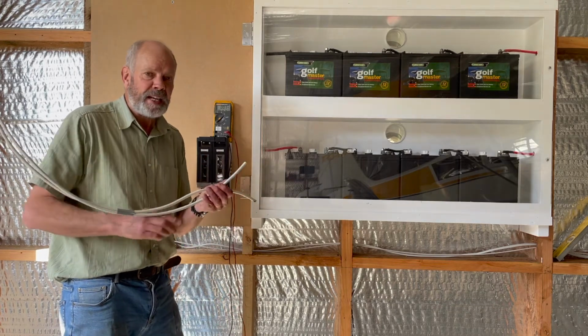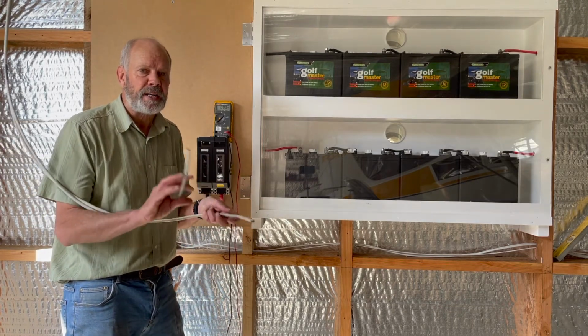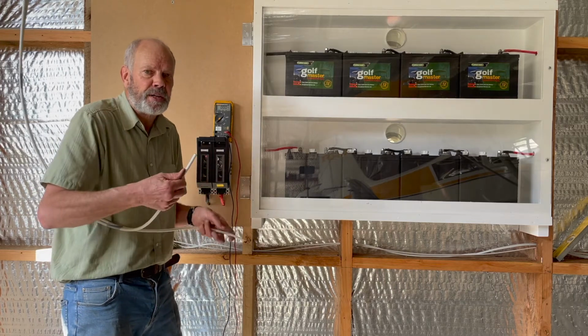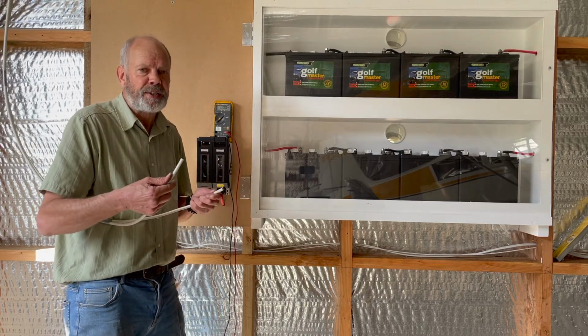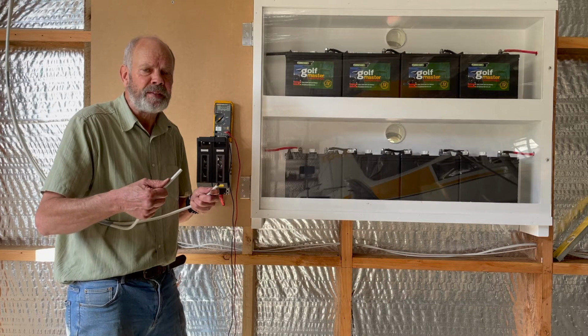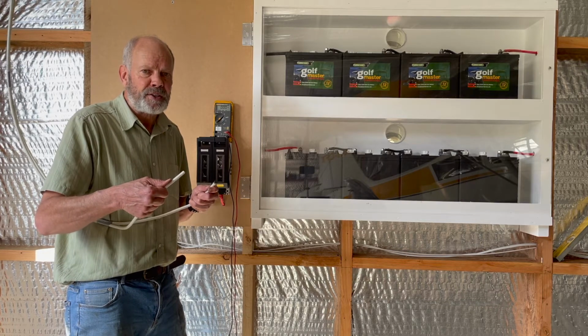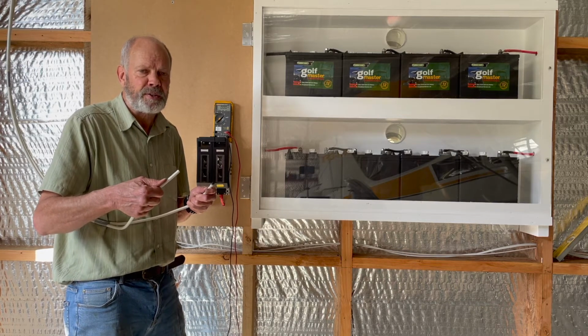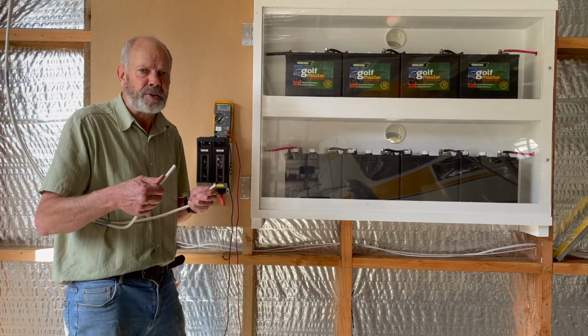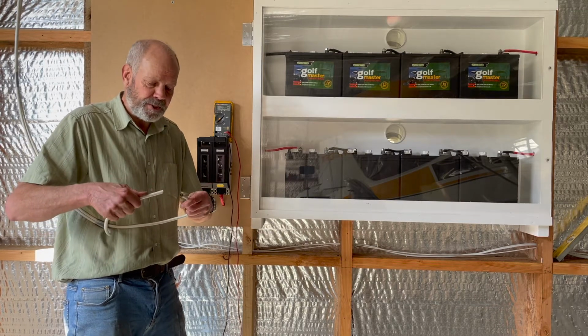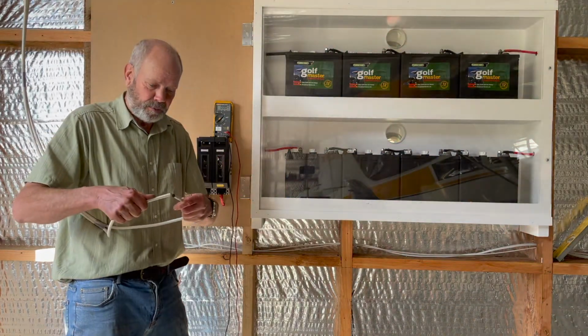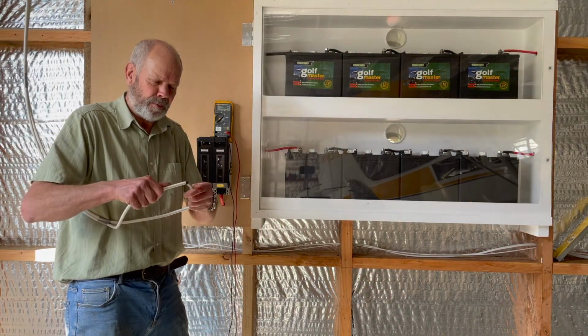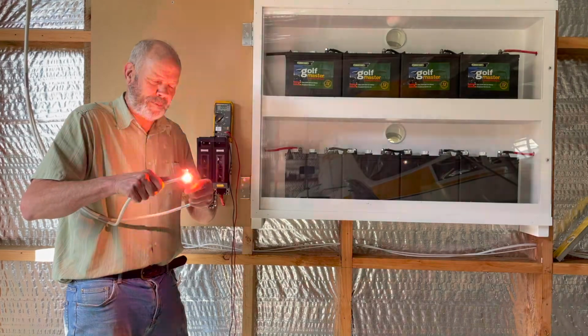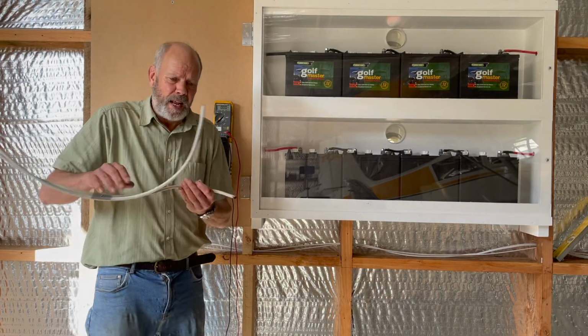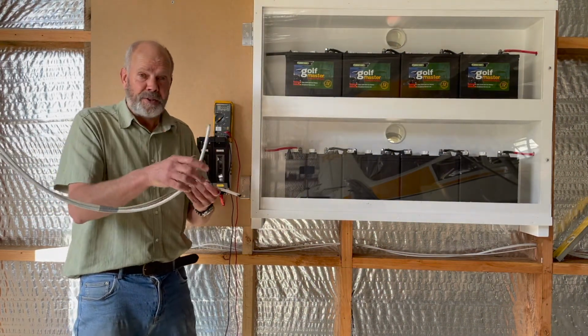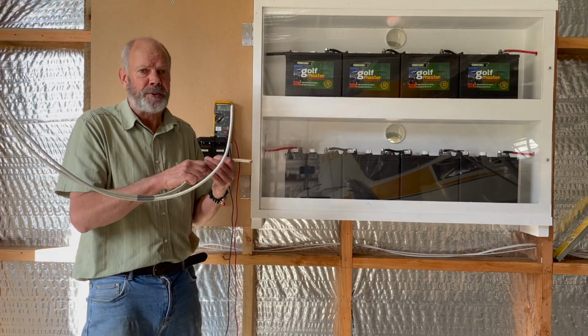Now, a solar panel you can actually short circuit together, and this is why just a switch on the roof is required, not a circuit breaker, because a fault in the array will not trip that circuit breaker. If the fault in the array tripped that circuit breaker, the circuit breaker would also trip as it provided the current to the regulator. If I touch these together, I'll get a welding-type current, and it doesn't hurt the solar panels. Short circuiting solar panels doesn't hurt them.